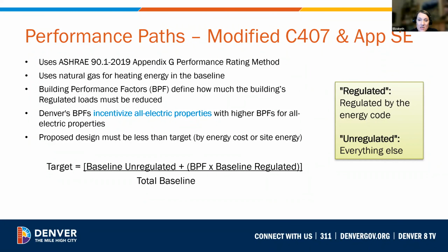The ASHRAE 90.1 Appendix G modeling methodology uses building performance factors to set targets for how much the building's regulated loads need to be reduced. Then the proposed design simply needs to have energy costs or site energy less than our target using this formula here.